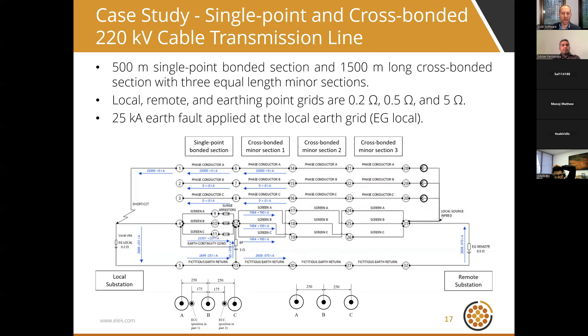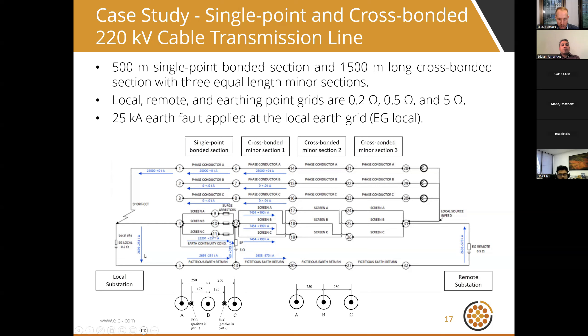In this case study, the prospective earth fault current level is 25,000 amps — quite high. If designing the local earthing system on the left-hand side to handle 25,000 amps, it would be very difficult to achieve safe touch and step voltages. By modeling the transmission system, it was found that approximately 2,500 amps — a little over 10% of the prospective fault current — will realistically enter the local earthing system. That is all that needs to be dealt with when designing the earthing system.